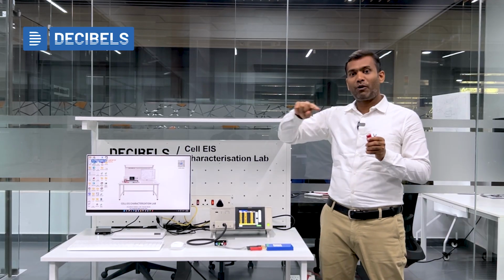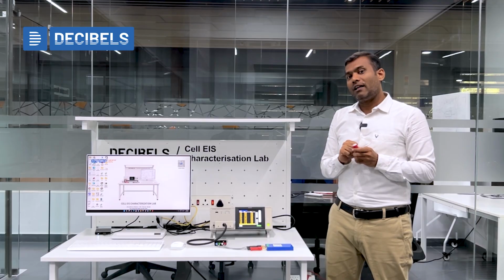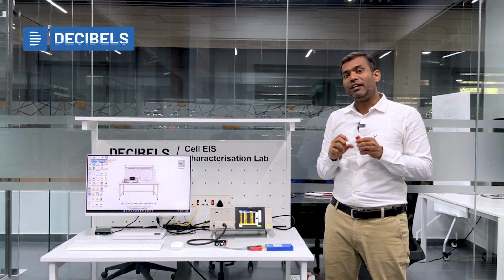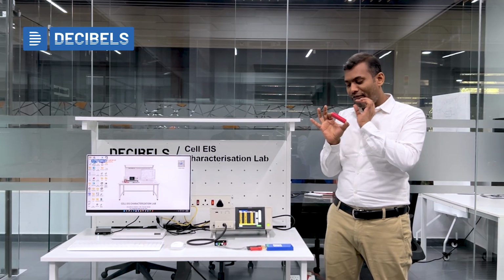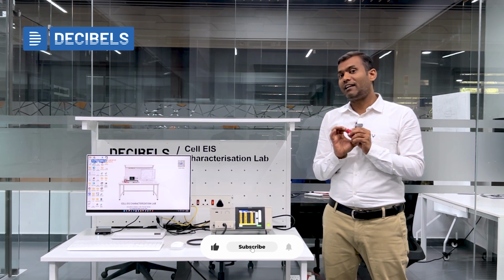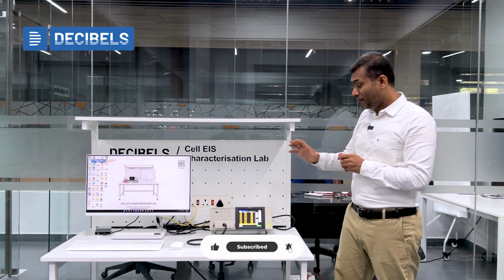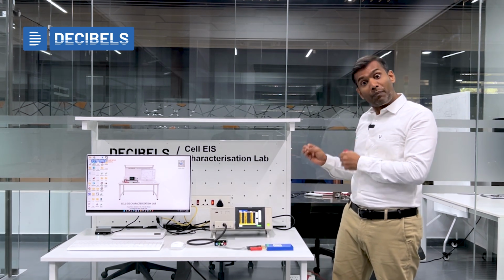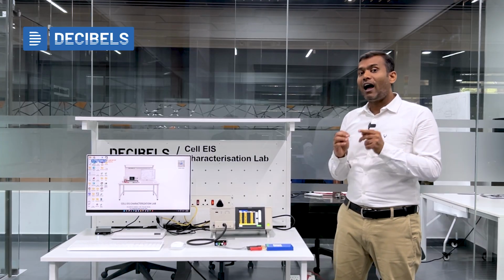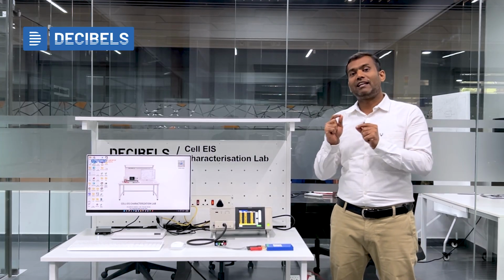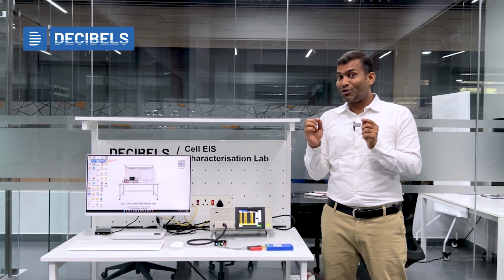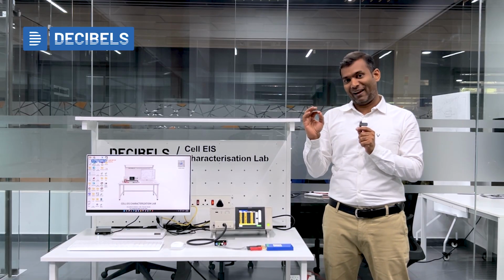Now, when you do that frequency sweep across a wide range of frequencies, you get to read the very detailed characteristics of the cell and what's happening inside the cell. So with the help of this unique test approach, you can study very clearly how the cell is degrading and also what component of the cell is degrading, right? And that's one of the components in place.